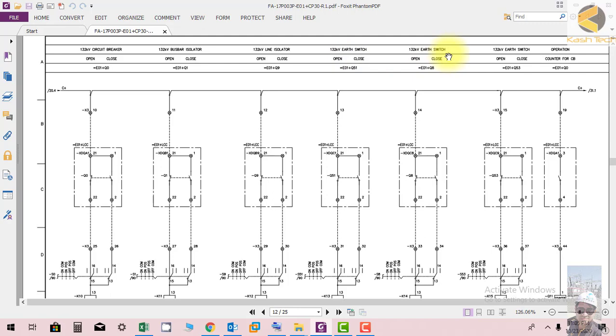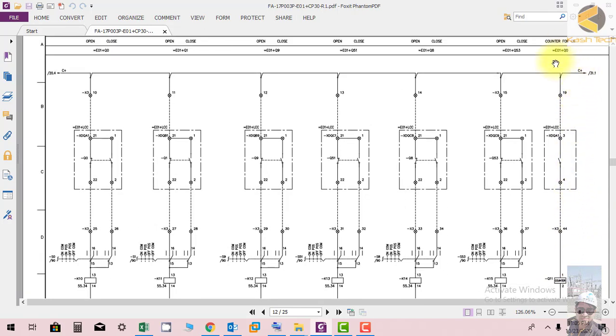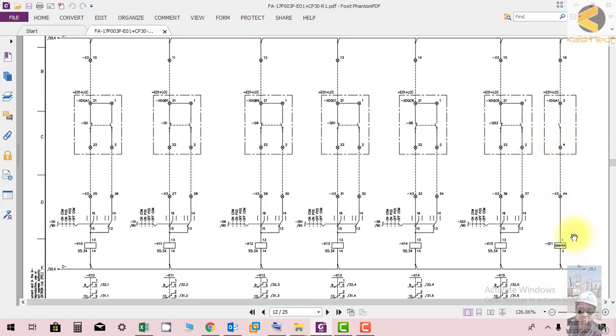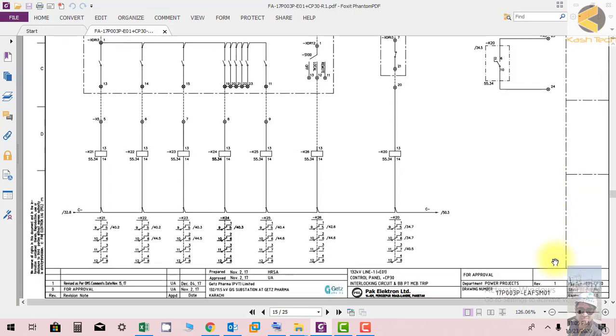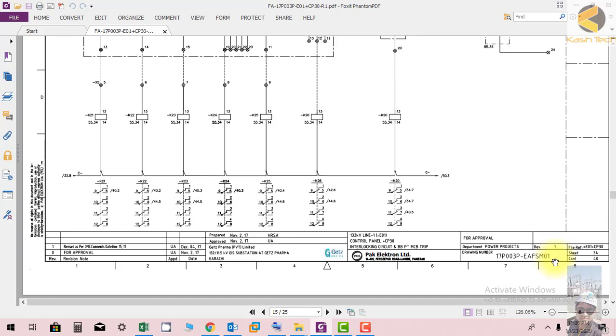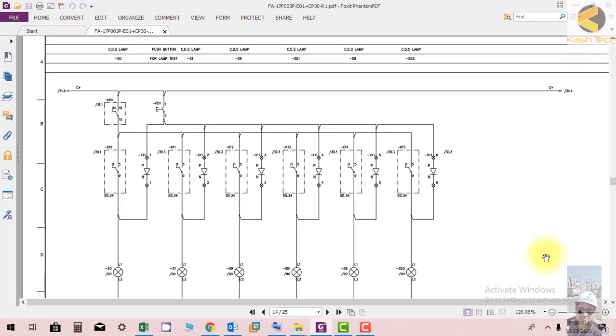There are additional indications in the drawing for the line isolator and earth switches at 132 kV. Inside the mimic or control panel a counter is installed; whenever the breaker closes this counter works to record the total number of operations of the circuit breaker. This is the circuit of the flicker relay. The next lecture will be related to interlocking of circuit breaker, bus bar PT, and MCB trip. Thank you very much.